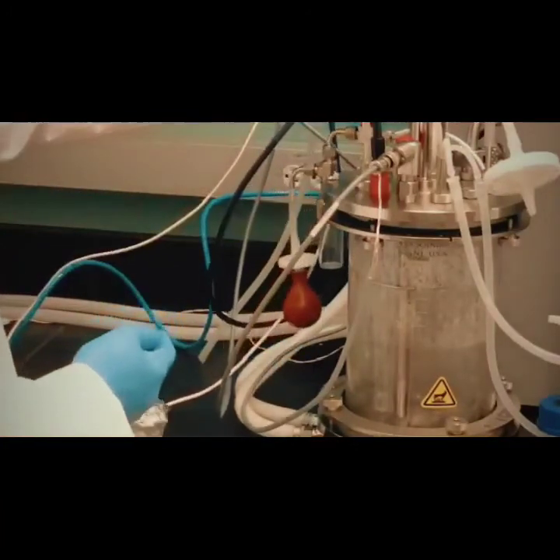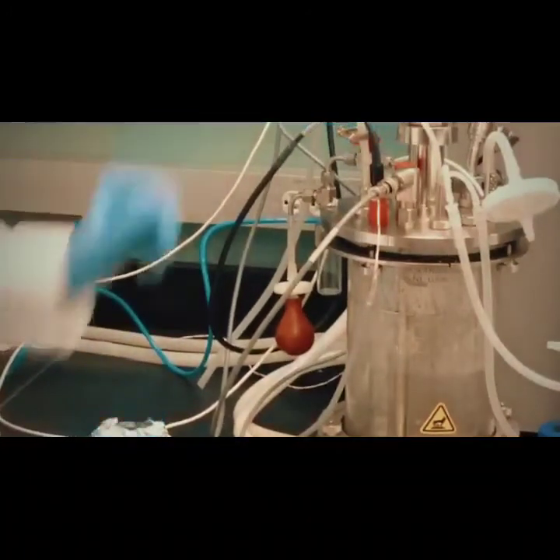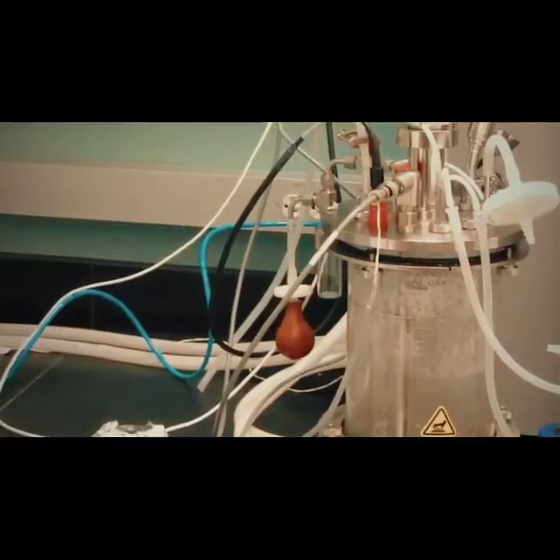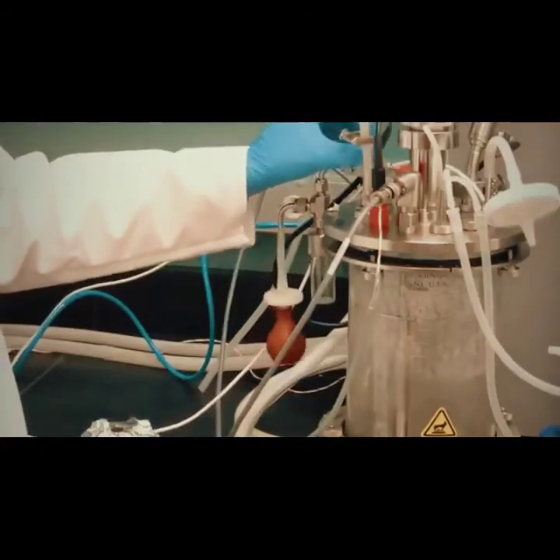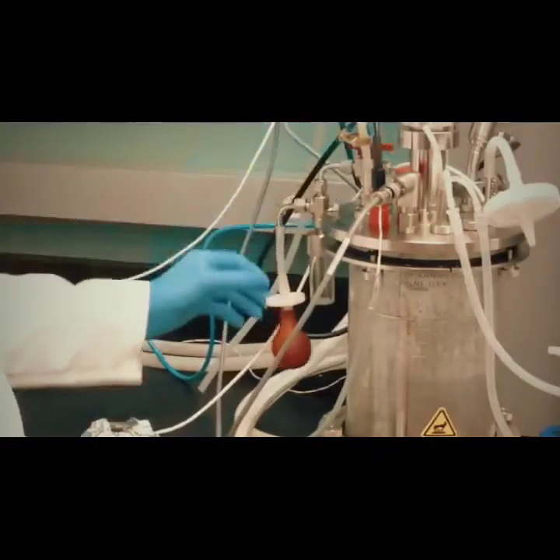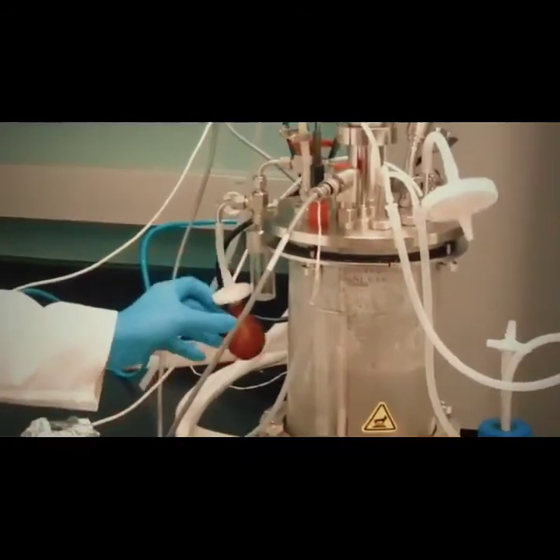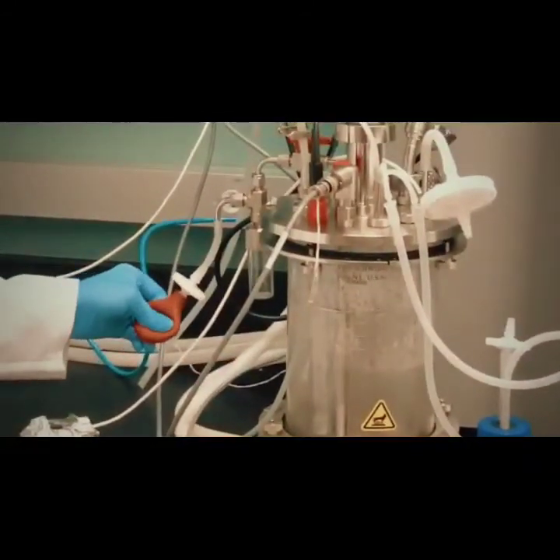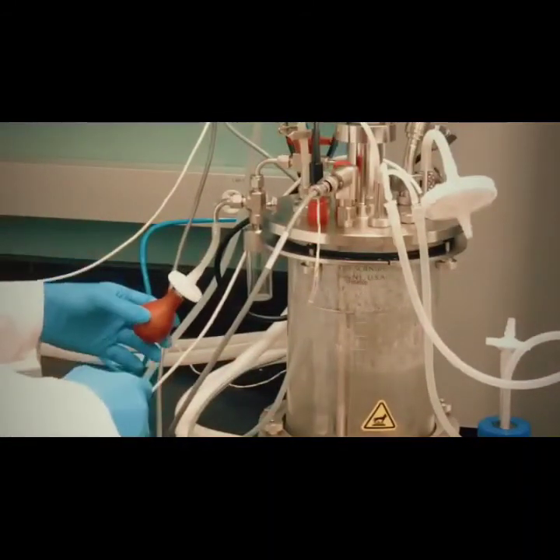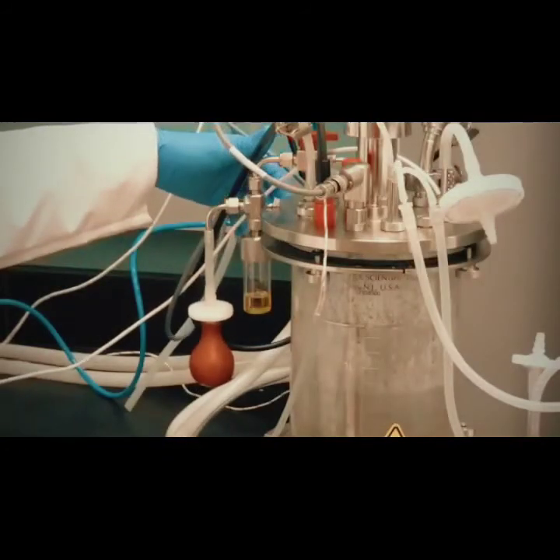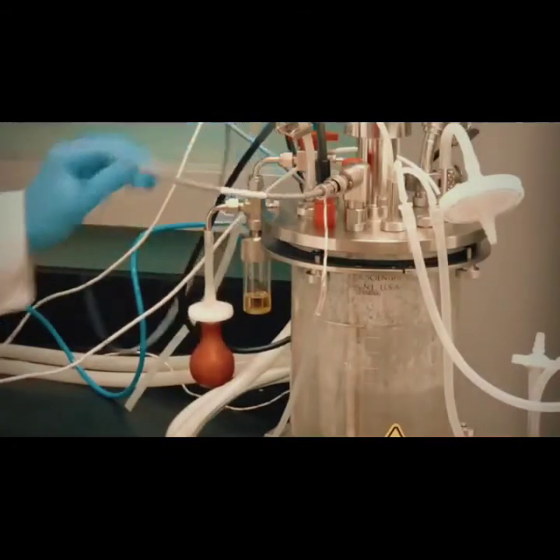Then, slowly release the red bulb. Sample should flow up from the attached vial. Close the red valve and replace the full sample vial with an empty one. Sample every hour. After the last sample, export trend data with a USB drive. See sample analysis.